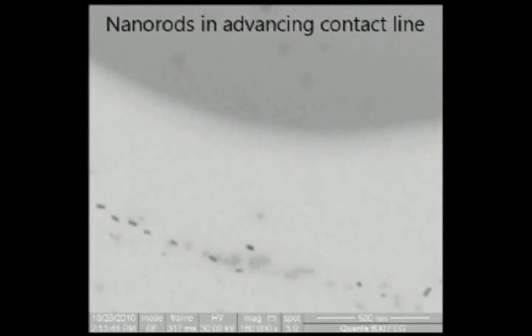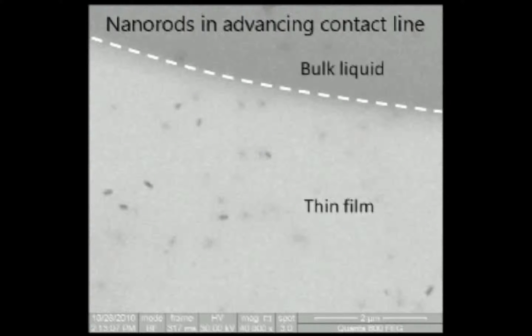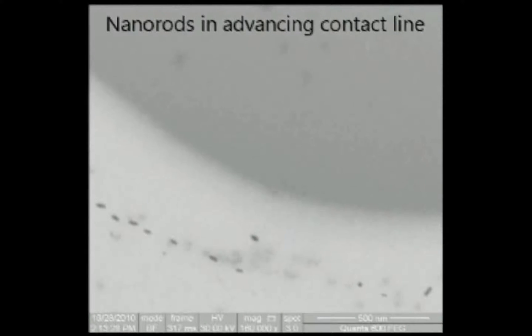One thing I'd like to point out of interest is after it zooms in, when it zooms out, I'd like you to look at what the interface is doing as we change the zoom. Notice that the interface was receding. Now, that dose rate that I talked about in terms of the electron microscopy, in this case for a STEM, is going to be a function of the irradiated area. So what happens in a scanning transmission electron microscope is you have a beam that's being rastered across your viewing area, and this beam has some current to it. It's a very small spot size on the order of a nanometer that is rastered back and forth very quickly. The way that you estimate the dose rate in this case is by taking that current that you're passing through and averaging it over the area. So as you zoom in, the area that you're dispersing these electrons becomes smaller, and your dose rate increases.